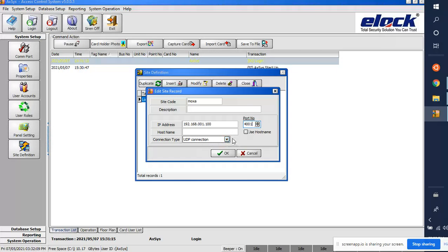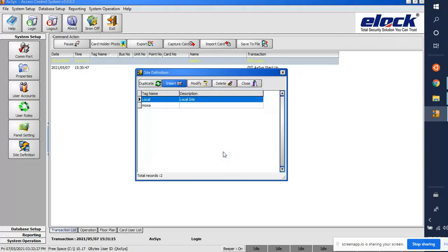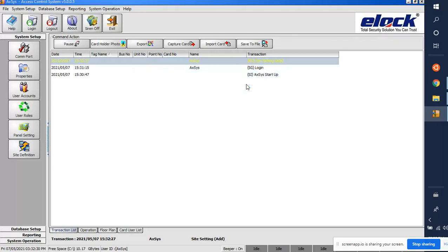The port number should be 4001, and the connection type should be UDP. There is some configuration to do in Moxa as well — I will explain that in the next video. For now, I'll set the IP to 192.168.1.100. Click OK and close this window.